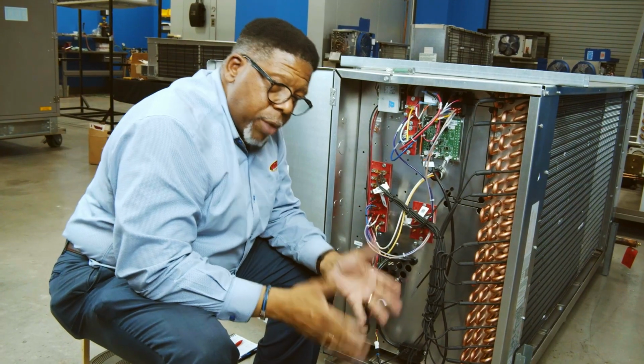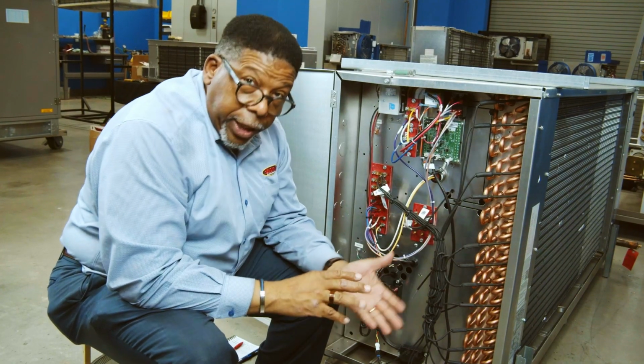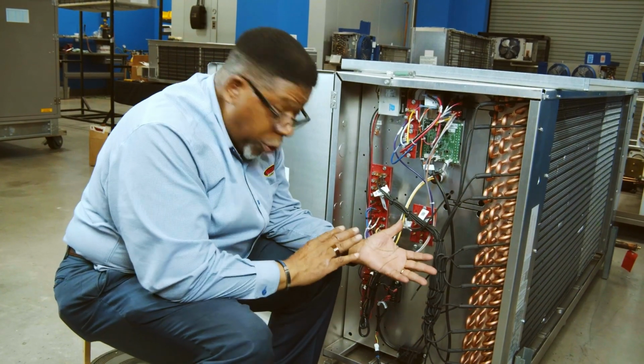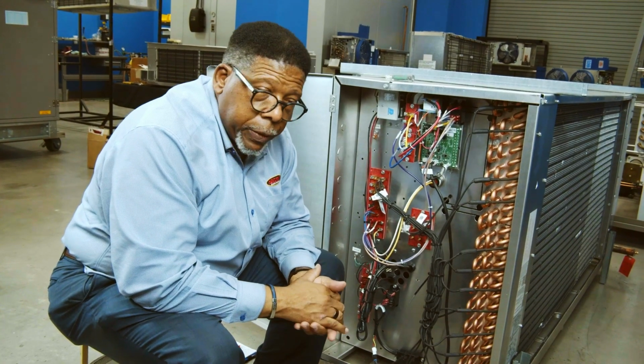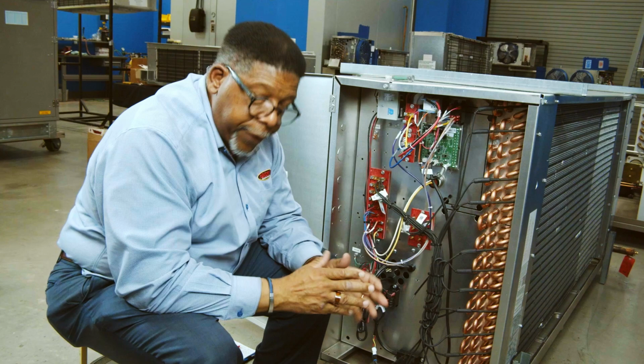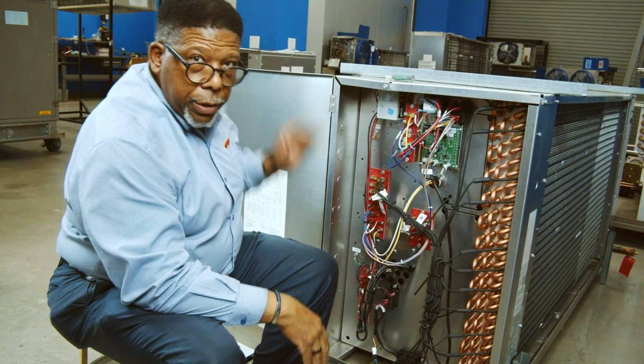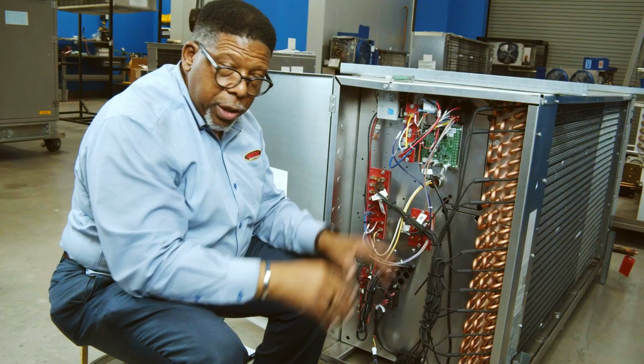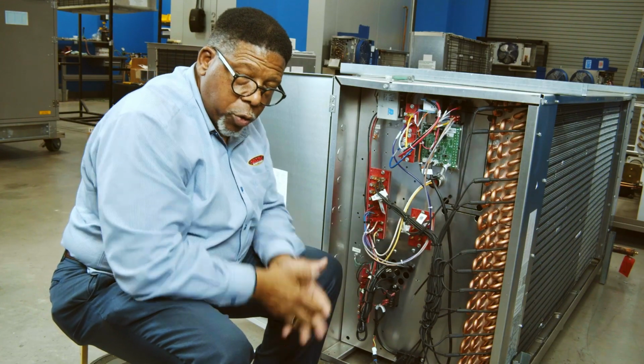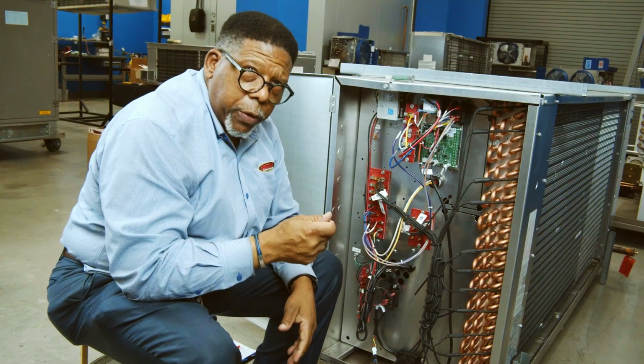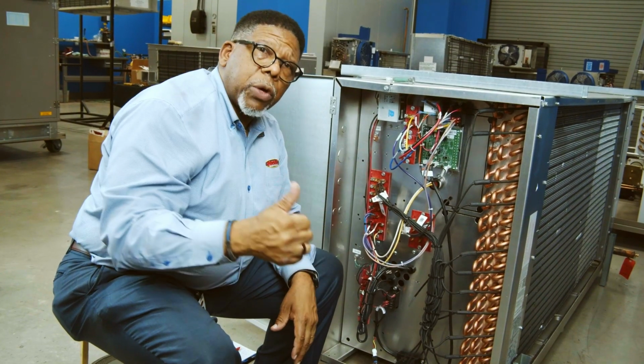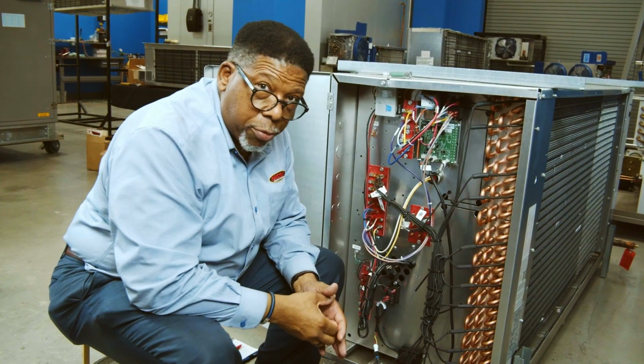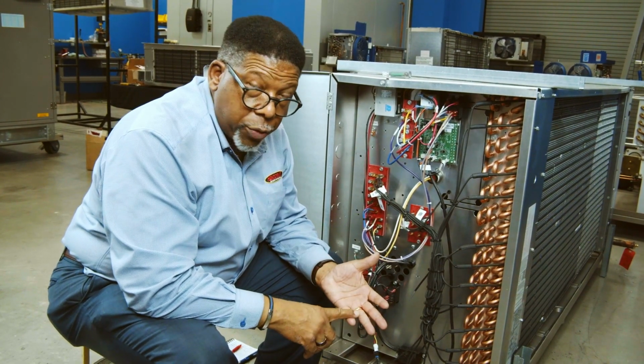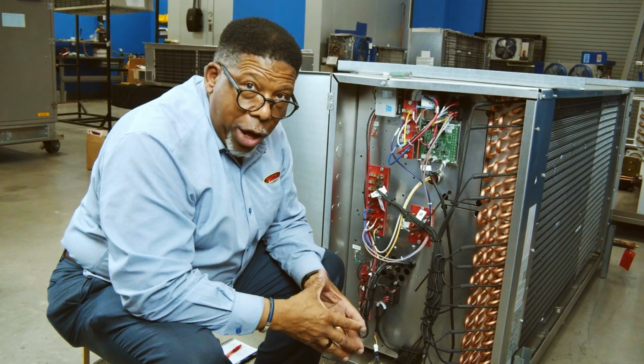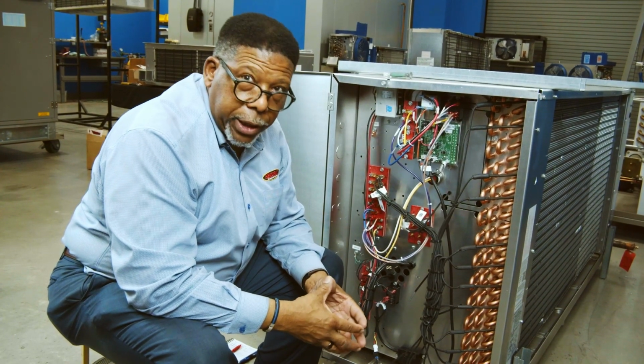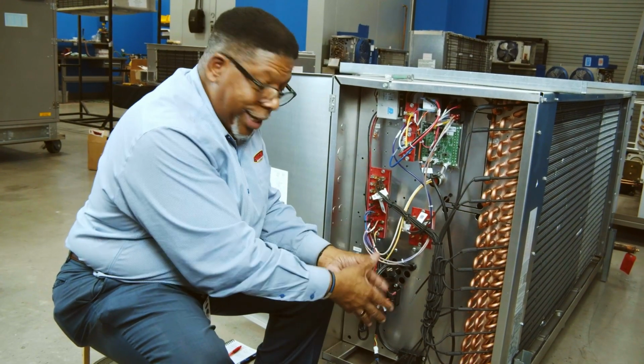Now, one more thing to close this up. You have to label this to make sure that everybody knows this has been converted to an A2L system. So when there's labels in your kit, affix them where they need to be on the front. If it's labeled Bohn or one of our other brands, have it somewhere near that so it says A2L equipped for that. And also the labels on not only the unit cooler, but also the condensing unit have to also be labeled properly. So do that with the charge and the refrigerant type, and you should now be ready to go set this thing up and it be legal and ready to sense a leak if necessary.